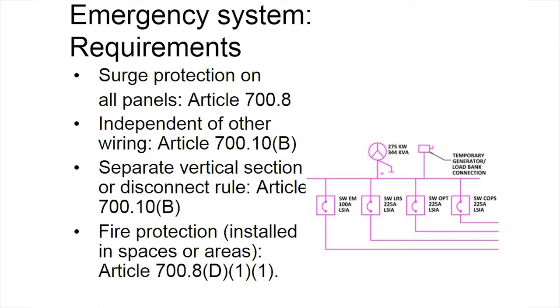Emergency wiring has to be independent from all other wiring. It can't occupy the same raceway or the same enclosure with any other wiring except where it absolutely has to. The exceptions would be devices with connections to both normal and standby power, like a transfer switch or, say, a dual source light fixture. Article 700.10 also calls for wiring from the emergency generator to the emergency system that is separate from wiring that serves other systems, but it does allow an exception if the transfer switches that serve emergency load are served from separate vertical sections in the switchboard or from separate disconnect switches from all the other loads.